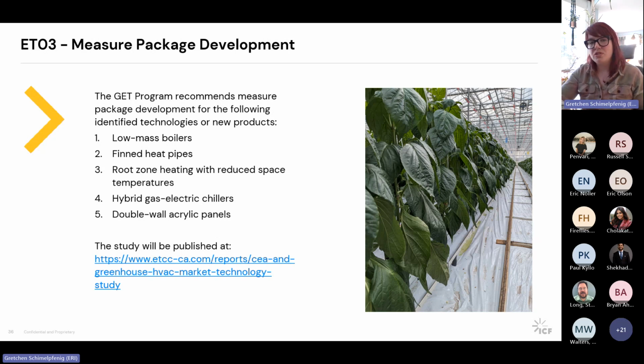But the general message is that design considerations for low mass boilers and finned heat pipes involve custom process equipment system designs that incorporate a lot of owner's project requirements, and require system details and diagrams that should be thoroughly explored, potentially by third-party consultants or commissioning agents. Overall, low mass boilers have the potential to save a lot of energy over unit heaters and have been demonstrated in the industry for some time. They're just not highly adopted in California yet.